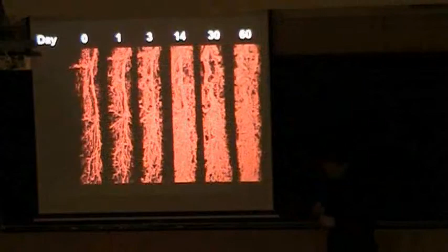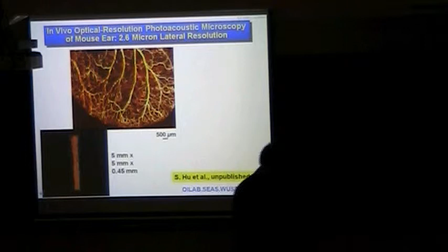We increased the resolution down to 2.6 micron, roughly about a factor of 2 improvement. And so that allows you to resolve even single red blood cells. And this is a 3D image showing in 2D projection view of the entire mouse ear without injecting any contrast agent. To do the same thing with micro CT using X-ray, you have to inject iodine-based contrast. Even with the contrast agent, you still miss capillaries. So this is a very natural tool for blood vessel imaging down to the smallest capillaries.